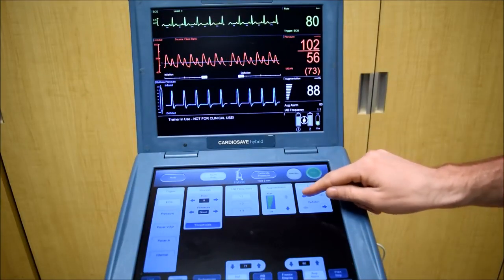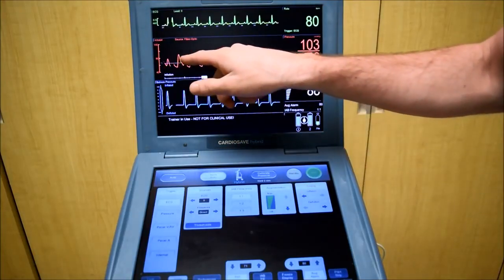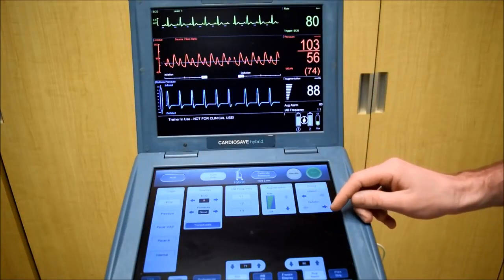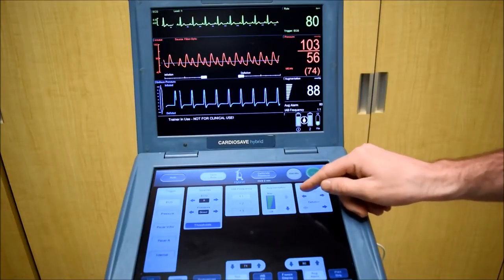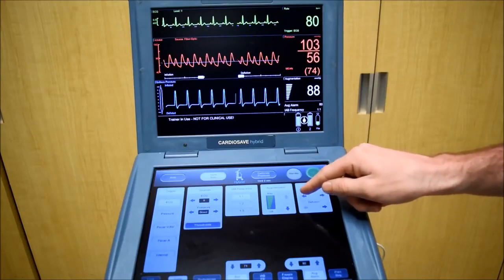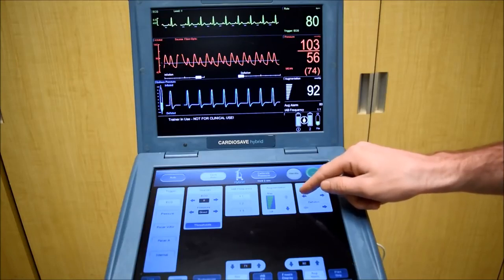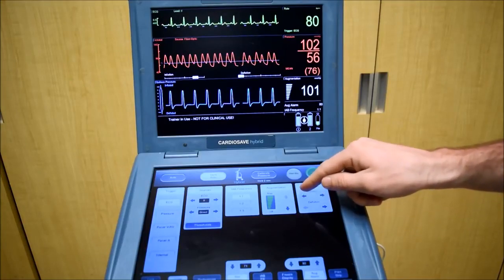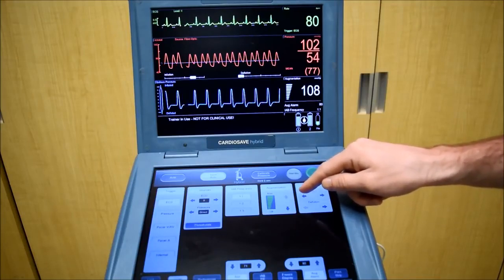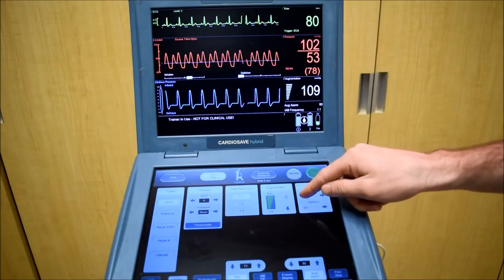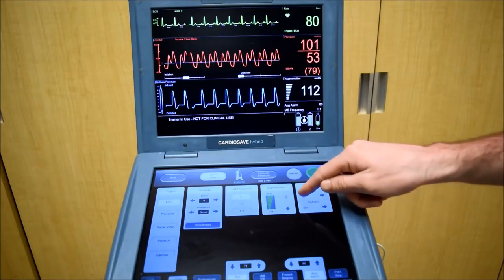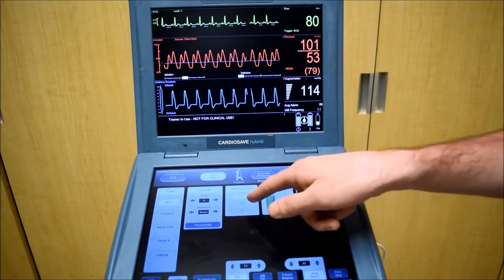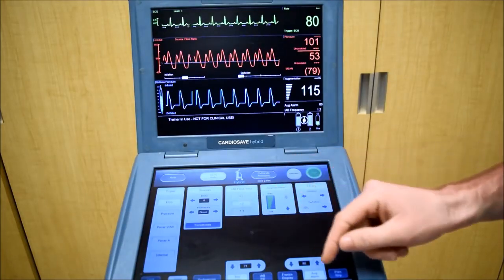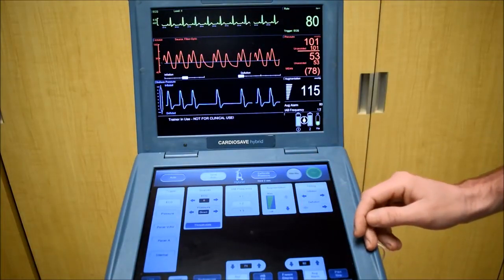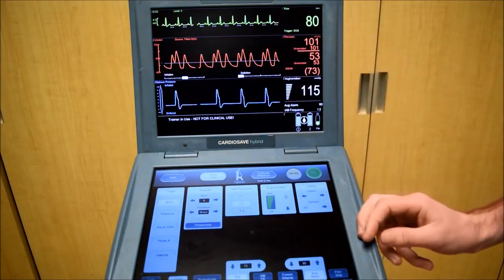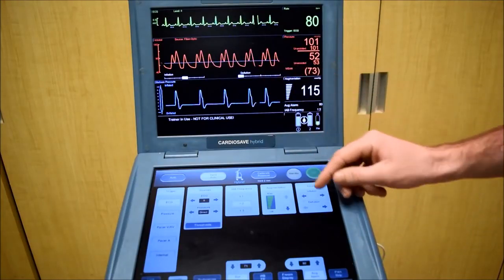Now we want to adjust our inflation timing so that we have a V, where we just start inflating right at the reference line or dicrotic notch. You'll notice as I move the inflation earlier, we get closer and closer to that reference line. If you have trouble seeing, it can also be useful to adjust the balloon pump frequency to 1 to 2. This will mean you will have one assisted and one unassisted beat. Right there is about good.